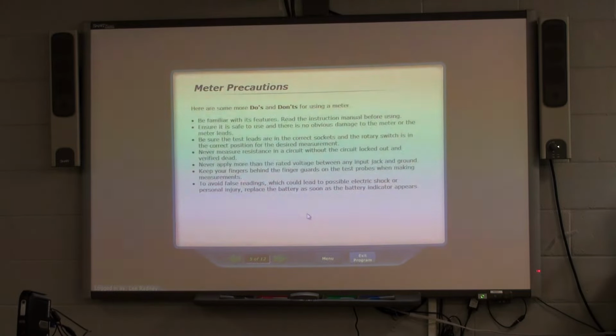Make sure your leads are in the correct sockets. That is an easy gotcha. The last thing you were measuring was current, and you're about to measure voltage, and you don't think about the fact that you have to move your leads back. You're on the job, you're in a hurry, you're trying to get done, you just measured the current and had to move your lead to do that. Then you go measure voltage and you're reading 0 volts because you're in the current section, and you forgot to move your leads back. There goes your meter. So always be sure: never measure resistance in a circuit without the circuit locked out and verified dead. Otherwise, you're going to be buying a new meter.